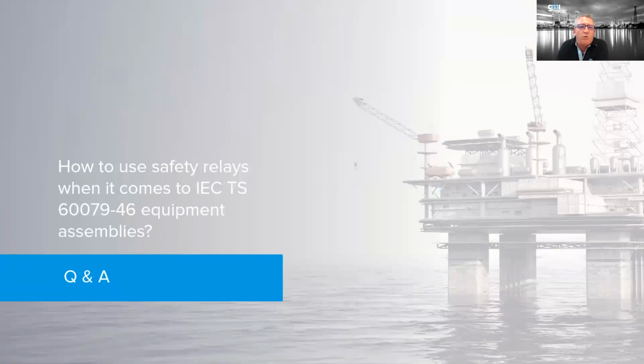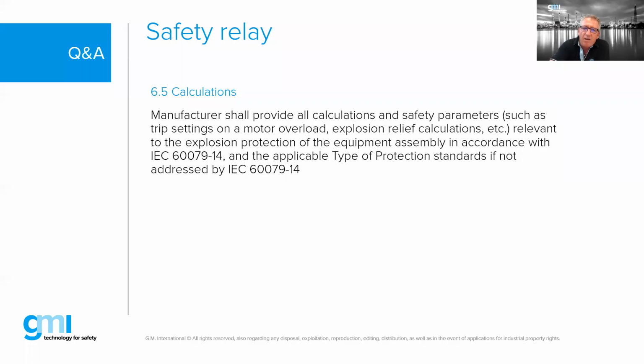The first one is how to use safety relays when it comes to IEC TS 60079-46 equipment assemblies. The TS 46 is an assembly technical specification that the IEC has come up with. This applies where, generally speaking, a good example is we have a motor and a motor starter. The motor could be EX certified, the motor starter could be EX certified, but have we matched the motor starter to protect the motor as a system? The technical specification dash 46 allows you to address that.